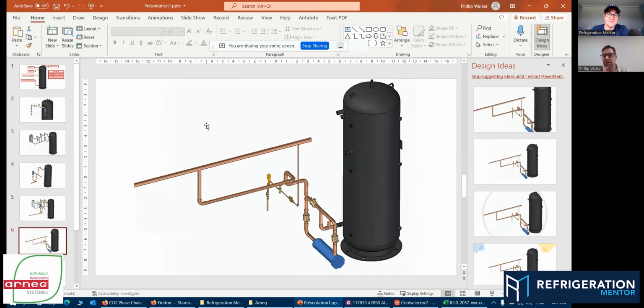So here we go. We've got our bottom liquid outlet. Fairly simple. As in any type of design, we're going to liquid feed into a manifold. You might realize there are a few little caveats here that are different from a standard design, and that's done intentionally for velocity. What you're going to see as well, which is maybe new to an Arneg system, is that we put sight glasses typically here, here, and on the manifolds themselves. It's because this is all liquid column. We want to ensure that we're getting good liquid flowing properly into the manifold.